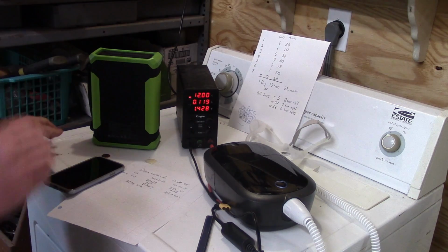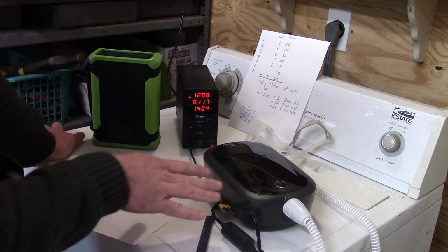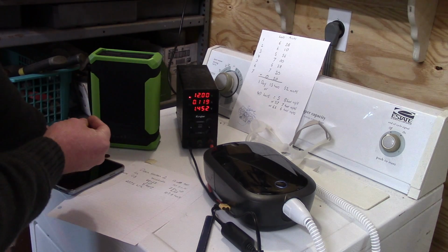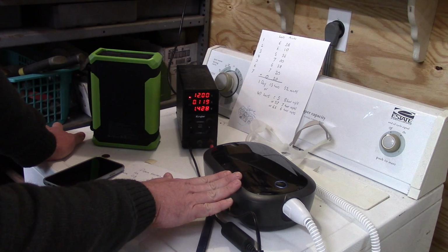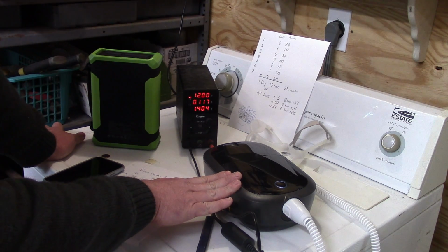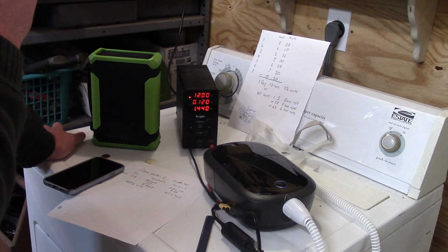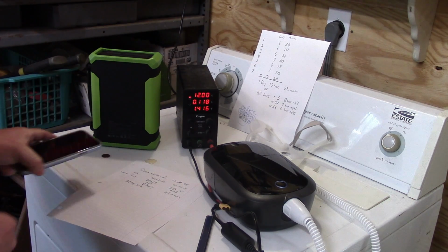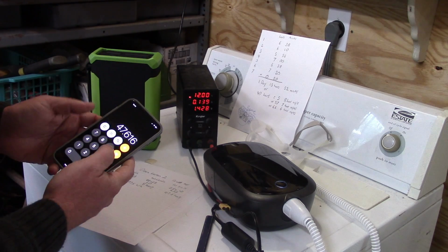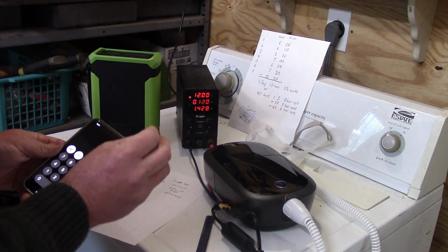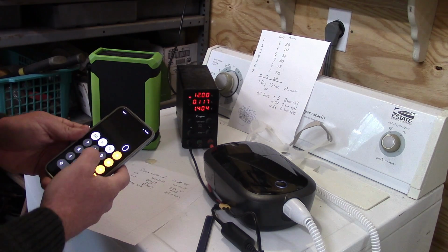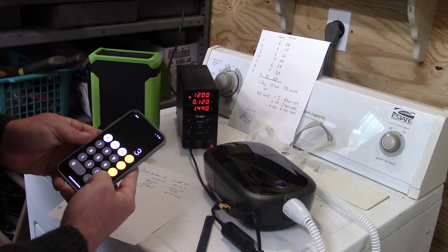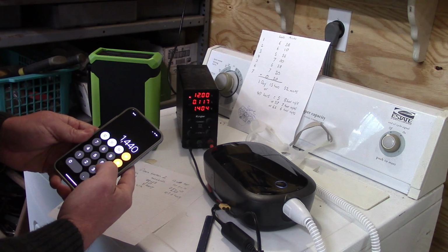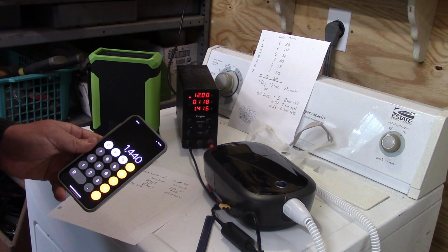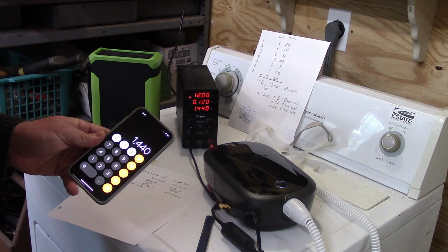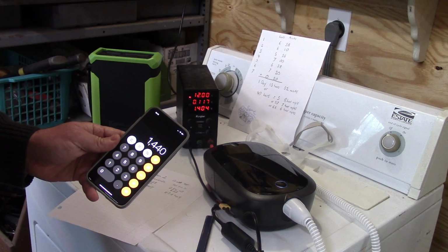And so what that means is that if you want to size a battery to your CPAP, you need to size the battery based off of how you want to use your CPAP. Are you going to be using it for heat and humidity? Then you're going to need a huge battery. So let's take our 60 watts per hour, and let's just make believe what size battery we need. Let's say we want to run our CPAP with heat and humidity for 3 8-hour nights. So let's go 8 hours times 3 days times 60 watts. That means you need a 1440 watt hour battery. That's a huge battery. That's almost 1.5 kilowatts.